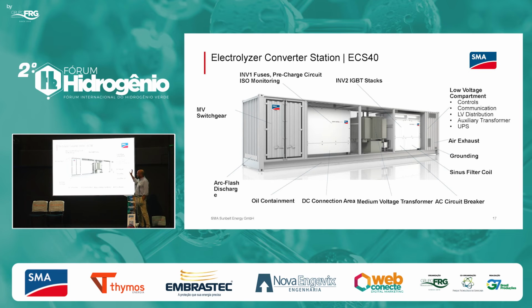But this is a complete biodegradable oil, and we also have an oil containment underneath. So for example, if I mount such a system in the middle of a city, I don't have to expect any problems because the only contaminating fluid inside the oil will not be spilled outside. Also, this oil has a very high flame point to ensure that if the transformer is burning, it doesn't penetrate the earth.